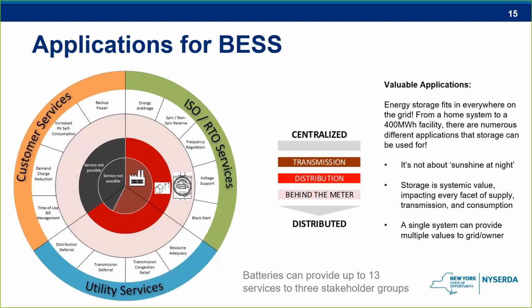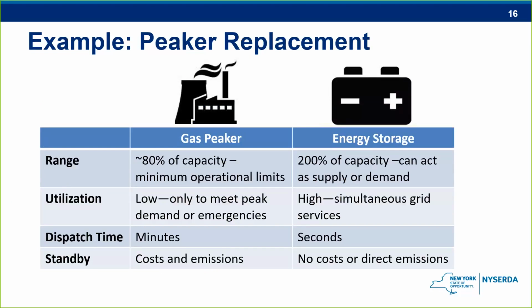It can serve as a source of electricity when generation sources are not available or some of them might be more expensive. And like I said before, it can help meet peak demand even for the grid, that time of day when demand for energy from the grid is at its highest. So think like a hot summer, late afternoon with air conditioners running at full blast in office buildings and homes all across the state. Typically, this additional electricity demand has been met with what we refer to as peaker plants. And also historically, these peakers have been fueled by gas. Energy storage, battery energy storage in particular, has the ability to replace gas peakers with a much higher range of capacity. They can provide simultaneous grid services while old peaker plants are generally slower to respond.